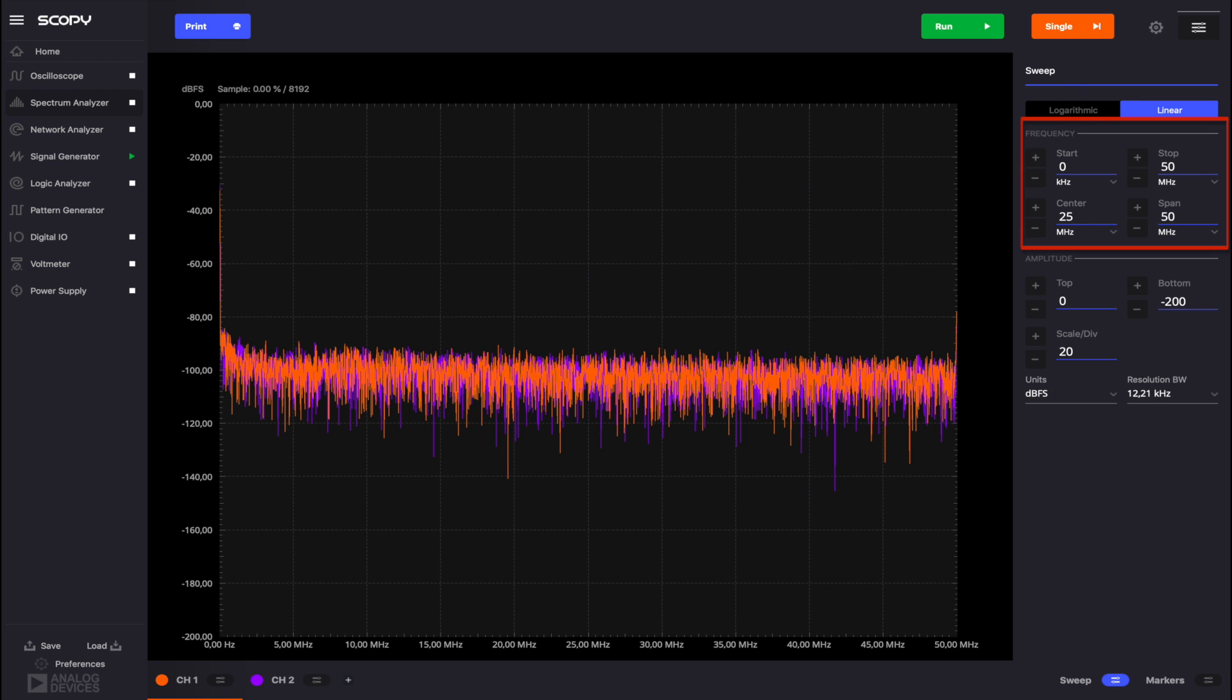In the Frequency tab, you can set the range of frequencies to be analyzed. This can be done either by setting the start and stop frequency values or by specifying the center frequency and the span. The spectrum may go up to 50 megahertz.